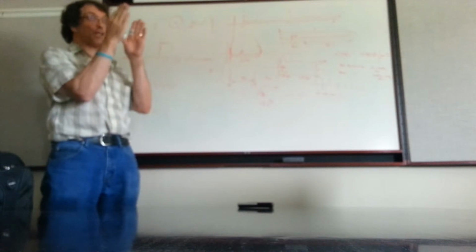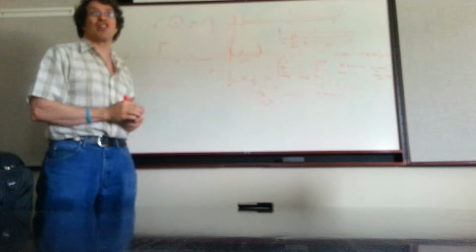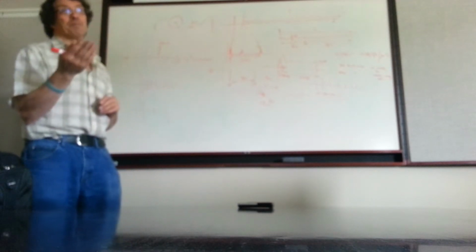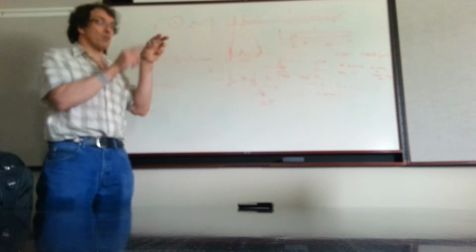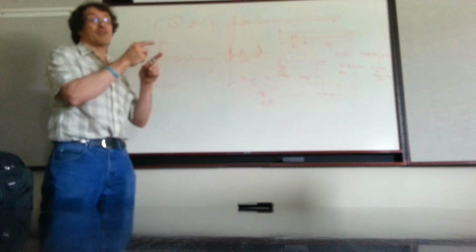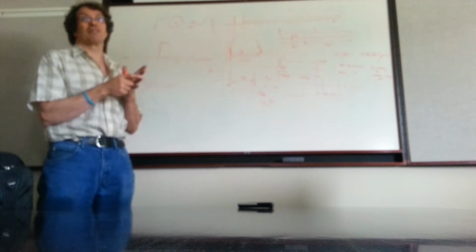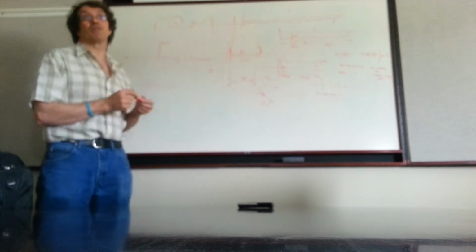If you then move the cursors, or the cursors were in the same place, it'll tell you that the distance has changed, because it's zoomed in. So then you can flip to time mode, and you can select how many microseconds it was from here to the fault. And then you know that it travels at 530 feet per microsecond. So you do a quick calculation, because it'll give you the microsecond distance, you can work out how many feet it was.